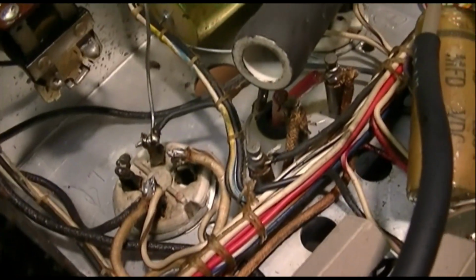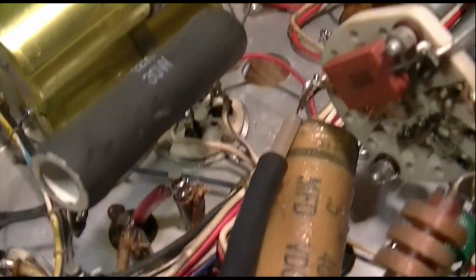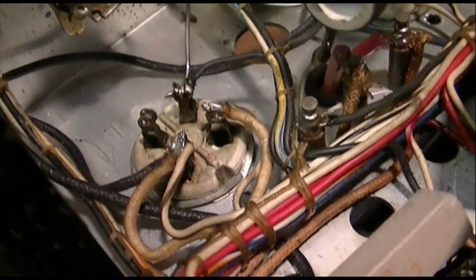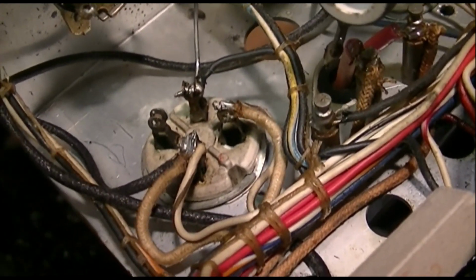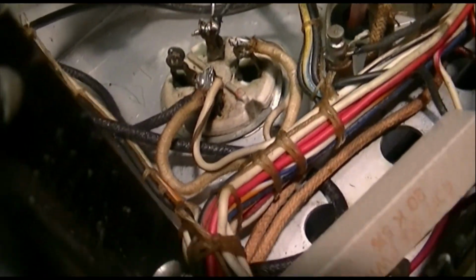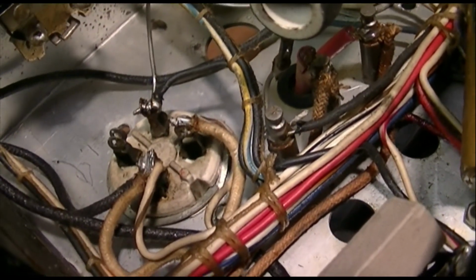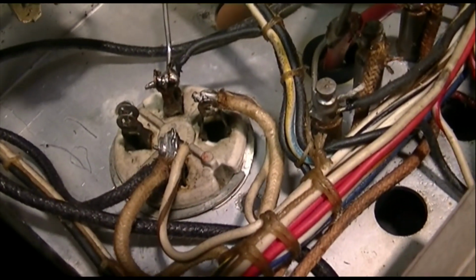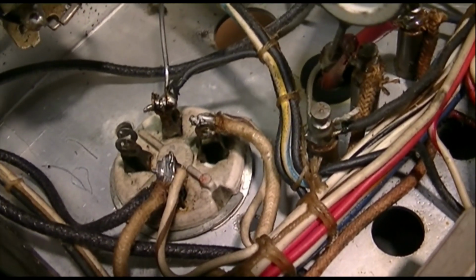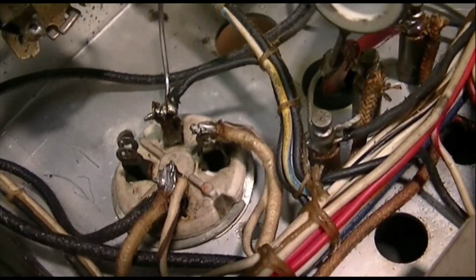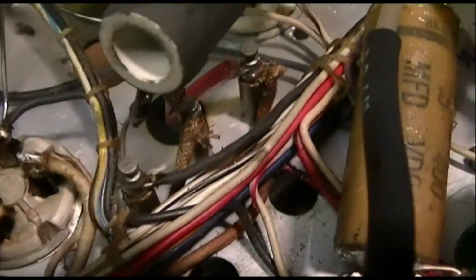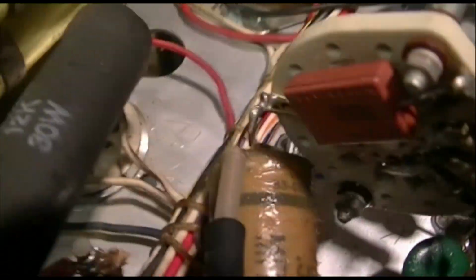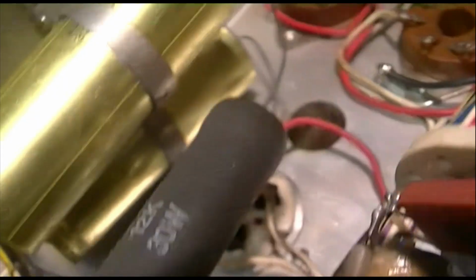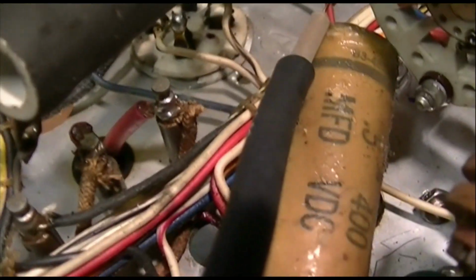Here's something that's often ignored—one of the most important maintenance aspects in any transmitter like this that has high voltage on it: you have to look. These are the rectifier tube sockets for the 866s, or whatever kind of rectifier it's got. It's very important. You can see that these are dirty. You need to get a toothbrush and some alcohol or solvent and get these things squeaky clean and inspect them visually. These tube sockets with high voltage on them can have 1,000 or 1,500 volts or whatever, depending on the kind of transmitter.